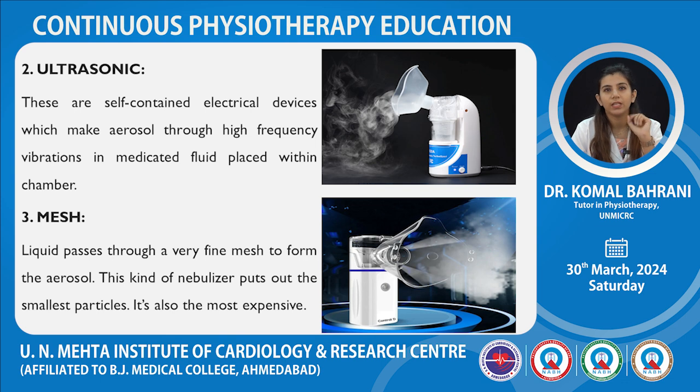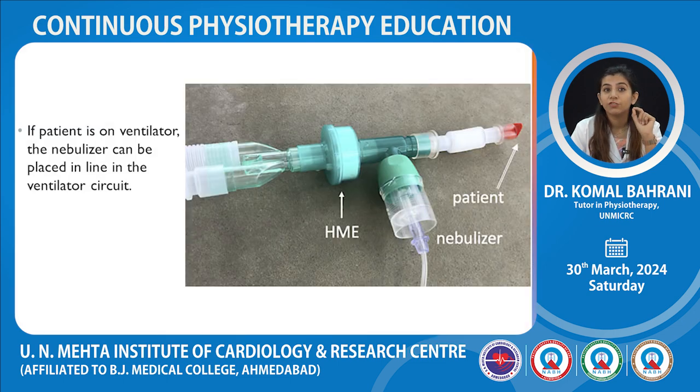These are self-contained electrical devices which make aerosol through high frequency vibrations in medicated fluid placed within the chamber. Mesh: liquid particles pass through a very fine mesh to form the aerosol. This kind of nebulizer puts out the smallest particles and it is also the most expensive. If the patient is on a ventilator, the nebulizer can be placed in line with the ventilator circuit.